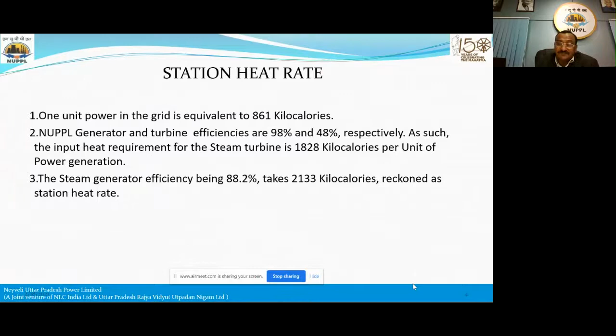Coming to today's topic, I would like to go from grid to the mine, because I came from mine to the grid. Now I will go in reverse. As we know, 1 unit of power in the grid is equivalent to 861 kilocalories of heat. NUPPL generator and turbine efficiency are around 98% and 48% respectively. As such, the input heat required for the steam turbine, with some efficiency calculation, is 1828 kilocalories per unit of power generation. The steam generator efficiency being 88.2%, 2123 kilocalories is required as station heat rate.